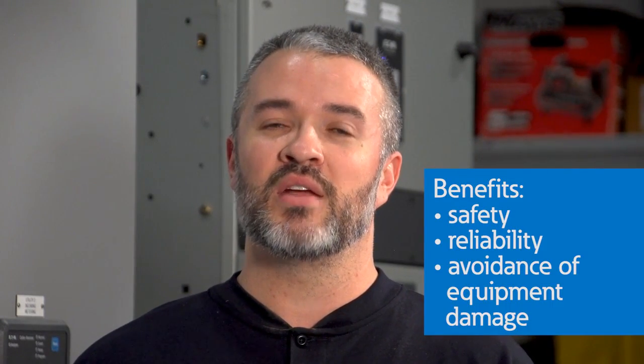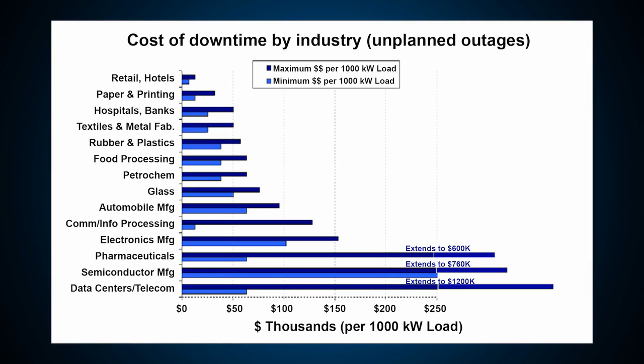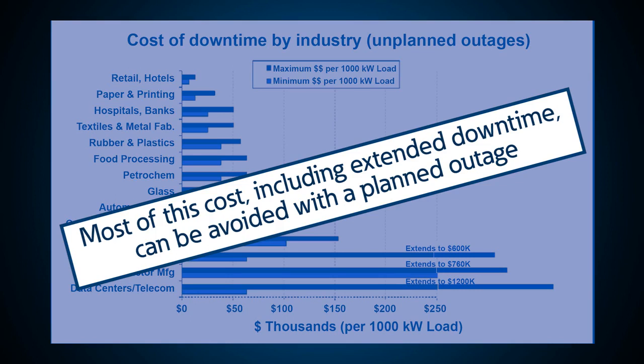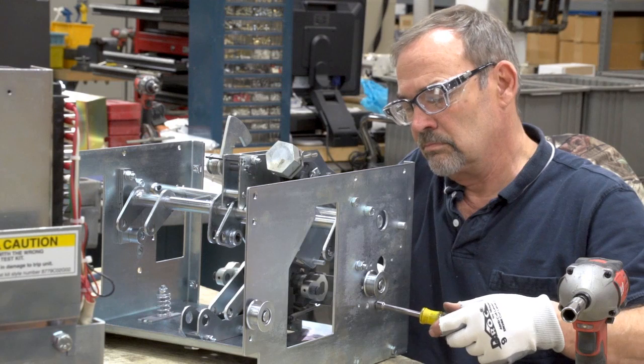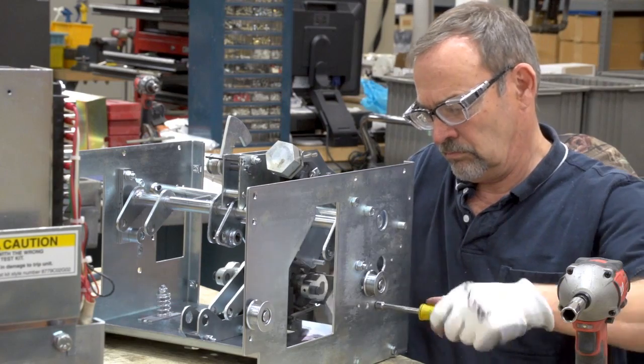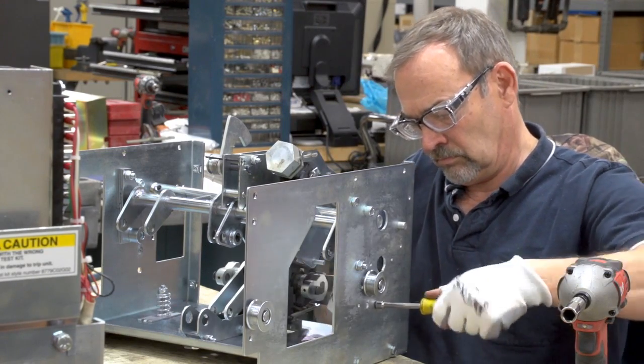There are three major benefits of testing and performing preventative maintenance on electrical equipment: improved safety, increased reliability, and avoidance of equipment damage. Outages are a major problem for anyone using electrical equipment, and usually, the more power you use, the more costly the problems are. A planned outage can be controlled with expected costs and expenses, but an unplanned outage is often significantly more costly and results in much longer downtime. Preventative maintenance during planned outages drastically reduces downtime and operating costs.